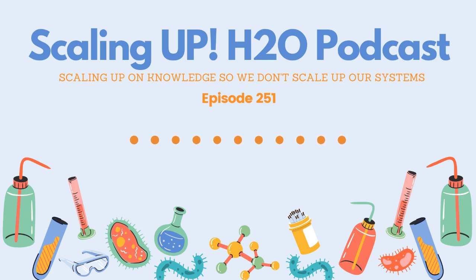Maybe everything in the system isn't as bad as we think, or as the controller thinks it is, and we need to fix a piece of equipment. So the first thing I like to do when I am interviewing the control equipment is I always check flow. I want to make sure that it's in a good line of flow and it's getting good flow. And then I start checking calibration. Are the readings that it is giving me the actual readings that I know are correct?